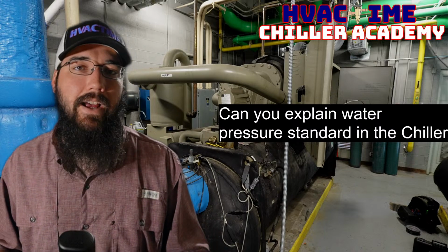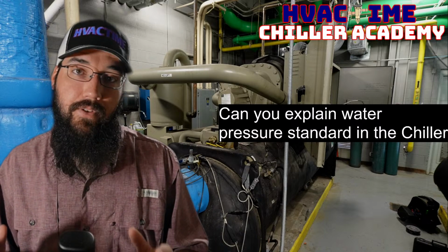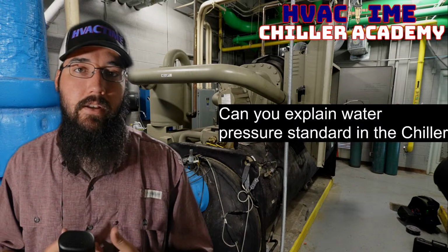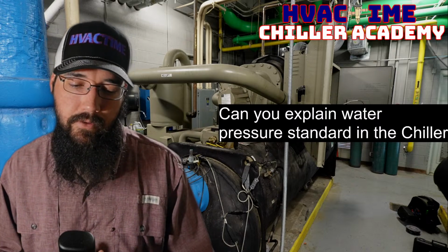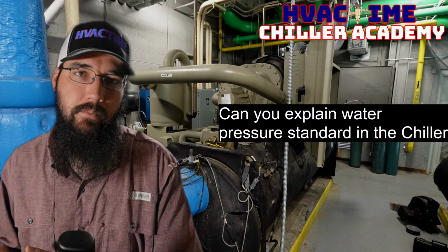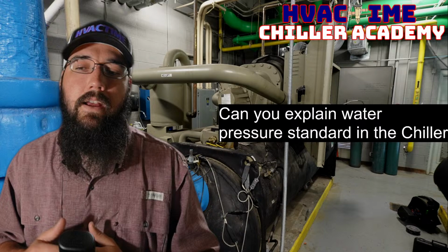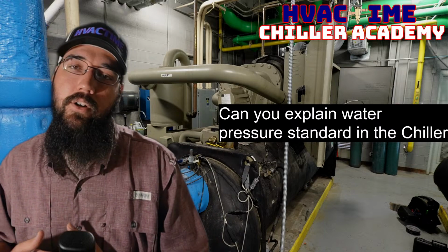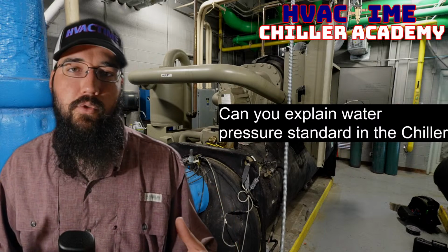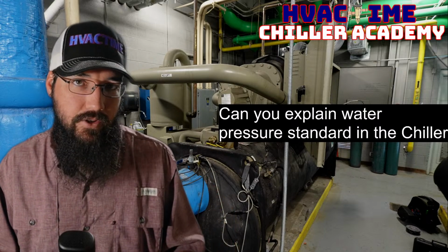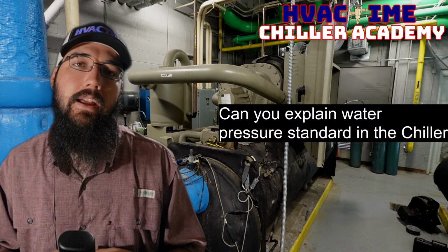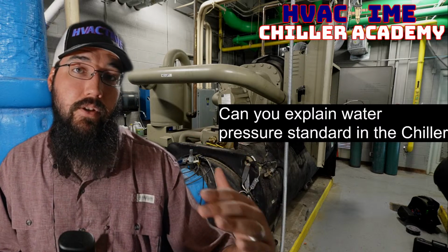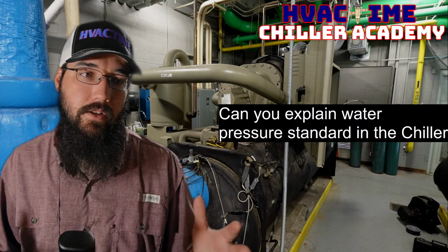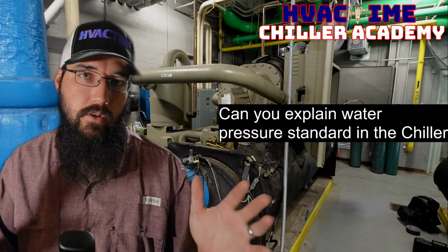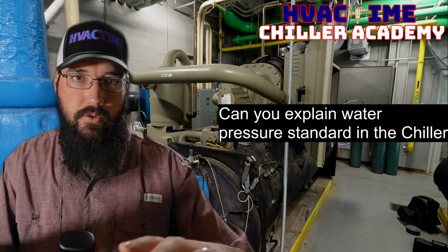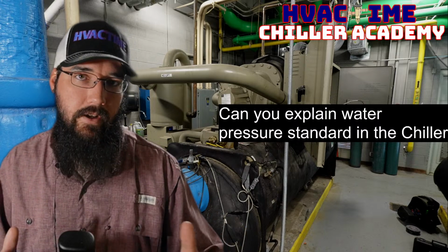If you can get access to the manufacturer's flow data for that particular machine, great. That's a very default answer, and let me talk that through a little bit further. In some cases, you're going to use the IOM, the Install, Operation, and Maintenance Manual. That will give you the information you're looking for in order to get the flow specs for that heat exchanger, and it'll be the heat exchanger specifically. What they'll have in there is a chart, and it may have a few different heat exchanger models. Sometimes they don't. Sometimes it's just one default chart for the majority of their heat exchangers. You'll just have to see how the manual's laid out and what they recommend, right?